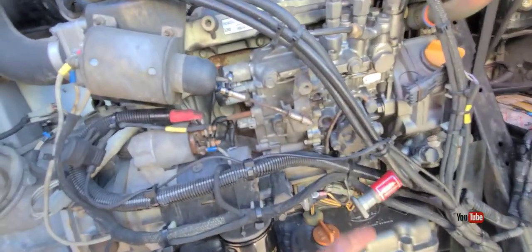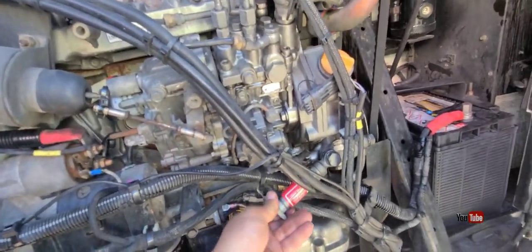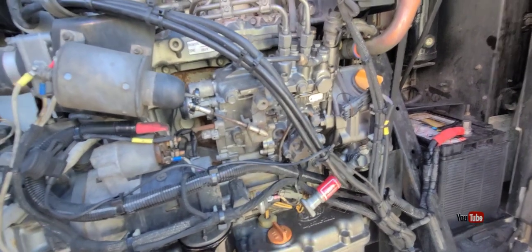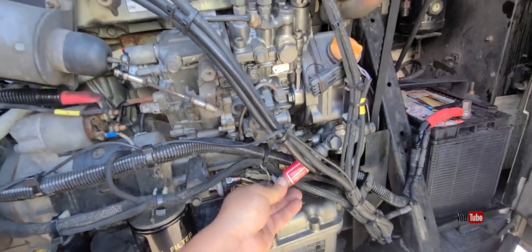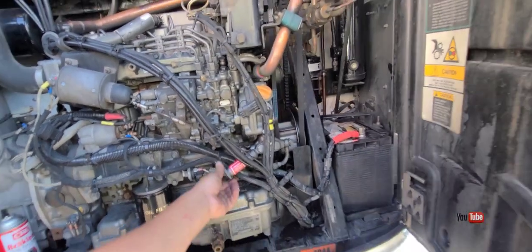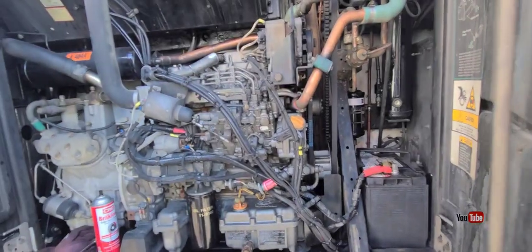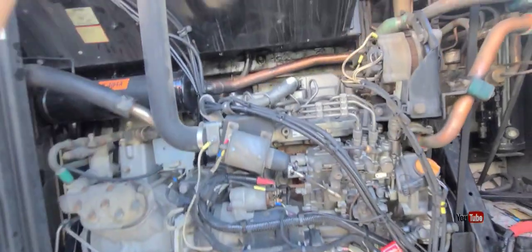Once you start priming it, this is gonna start to fill up, you know, or your drain or whatever you call that in there. It's gonna start to fill up. And once the unit starts, this is gonna get harder. It's gonna be harder for you to prime. That's normal as well. Let's see if it works now. Yeah, I got a cold start obviously, right? No fuel. It cranked right up because it's still hot in the lines, you know, it had fuel in the lines.